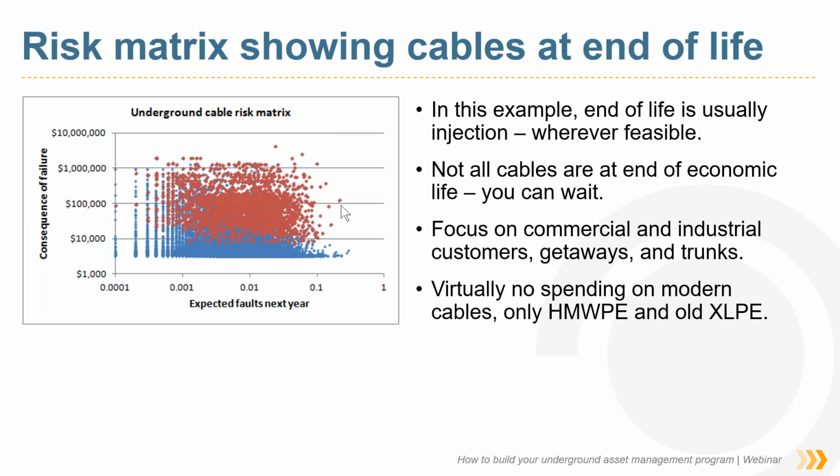And so this is an example taken from a real utility. What we found was that where injection was feasible, it was almost always preferable to replacement. And of course, not all the cables, even not all the old XLPE cables, are at end of life.